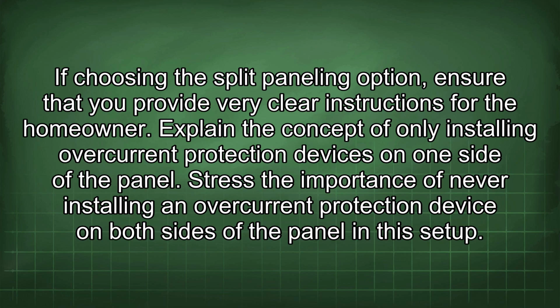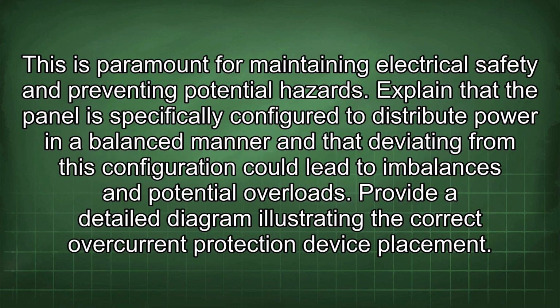If choosing the split paneling option, ensure that you provide very clear instructions for the homeowner. Explain the concept of only installing overcurrent protection devices on one side of the panel. Stress the importance of never installing an overcurrent protection device on both sides of the panel in this setup. This is paramount for maintaining electrical safety and preventing potential hazards. Explain that the panel is specifically configured to distribute power in a balanced manner, and that deviating from this configuration could lead to imbalances and potential overloads.